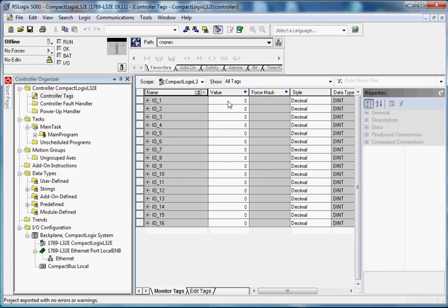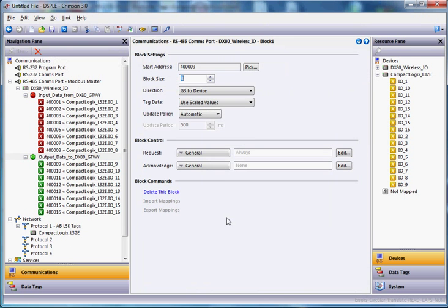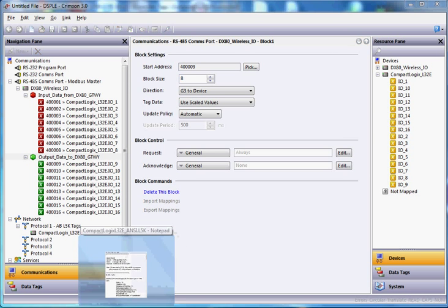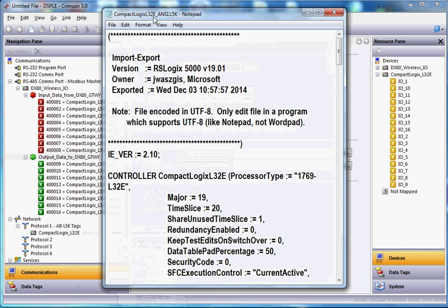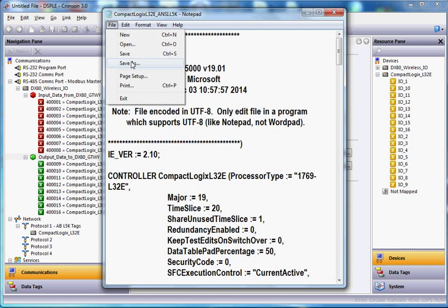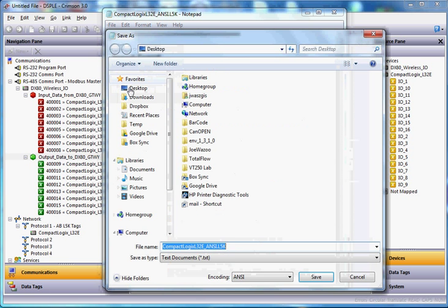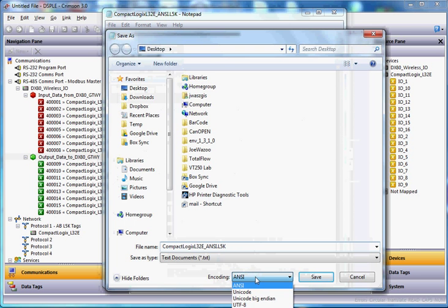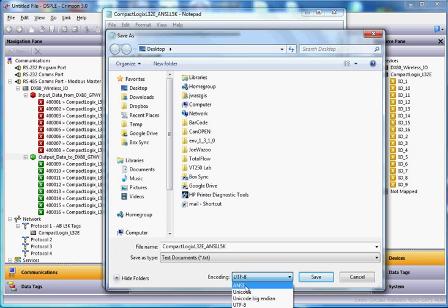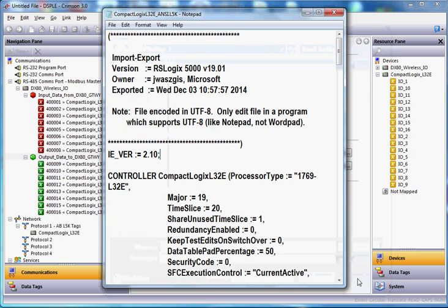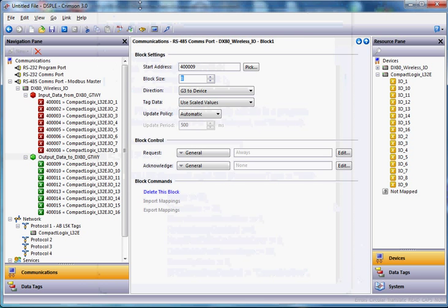So that's just a quick example of how you can use the Data Station Plus LE to do protocol conversion from Modbus into Allen Bradley's Rockwell software. The one key caveat to this is, depending on if you have a problem importing the L5K, you may need to go into Notepad and do File, Save As, and change the encoding here from the default UTF-8 to ANSI. Re-save the file, and then Crimson 3 will be able to import the program.